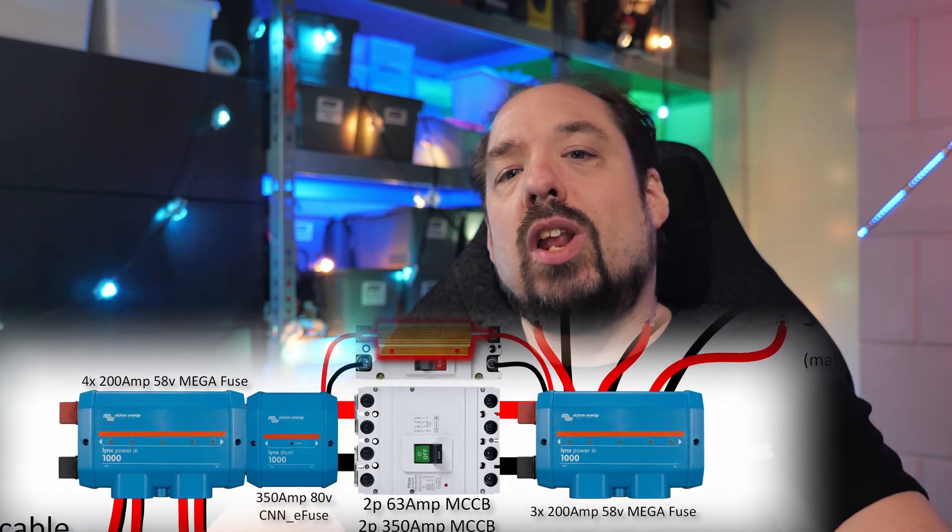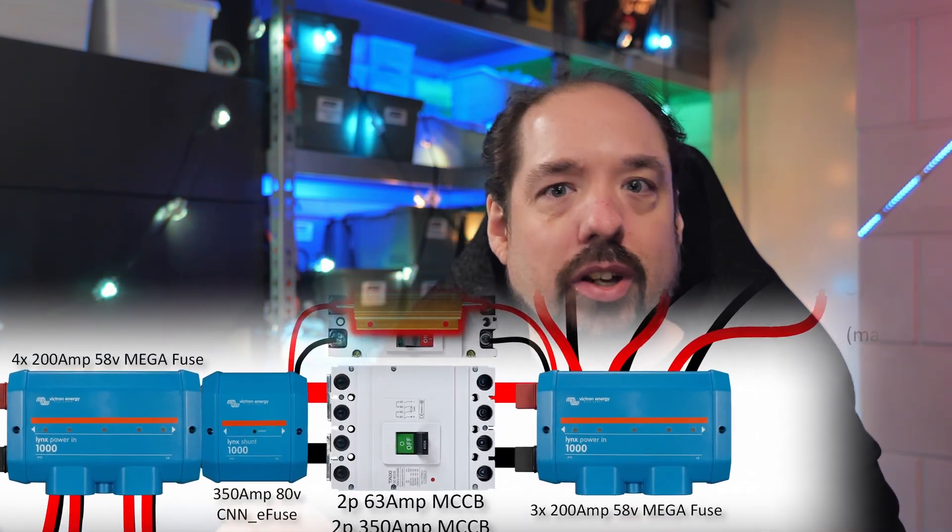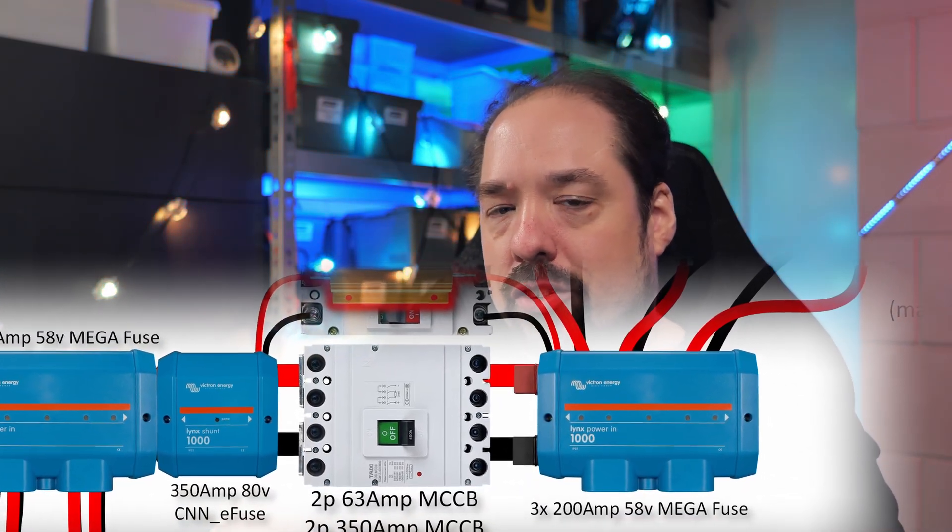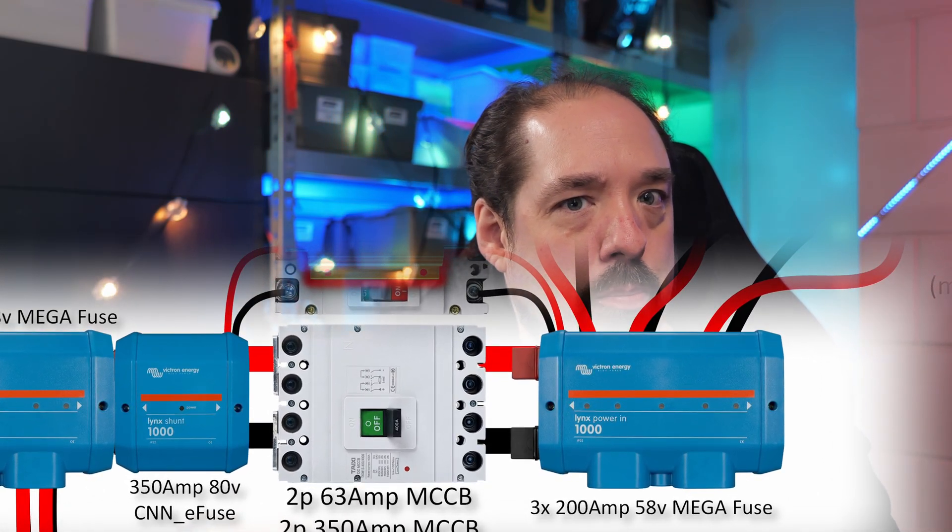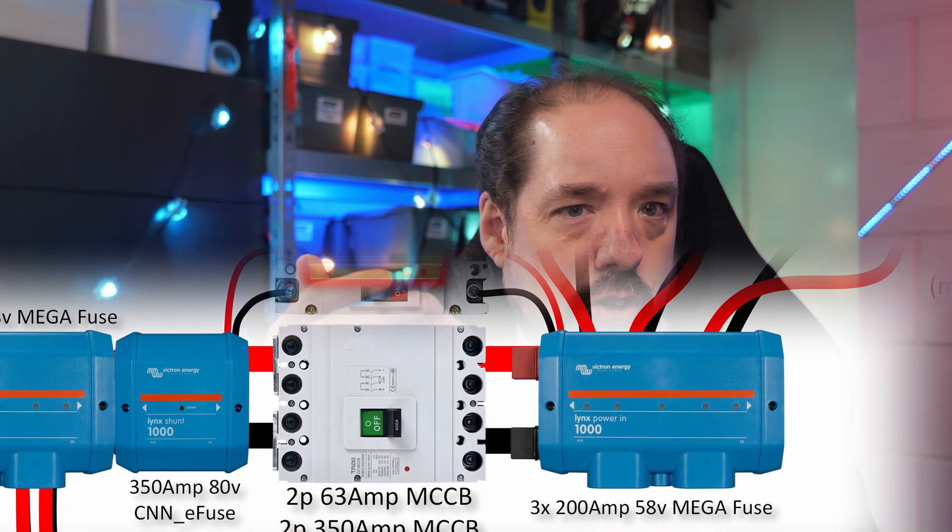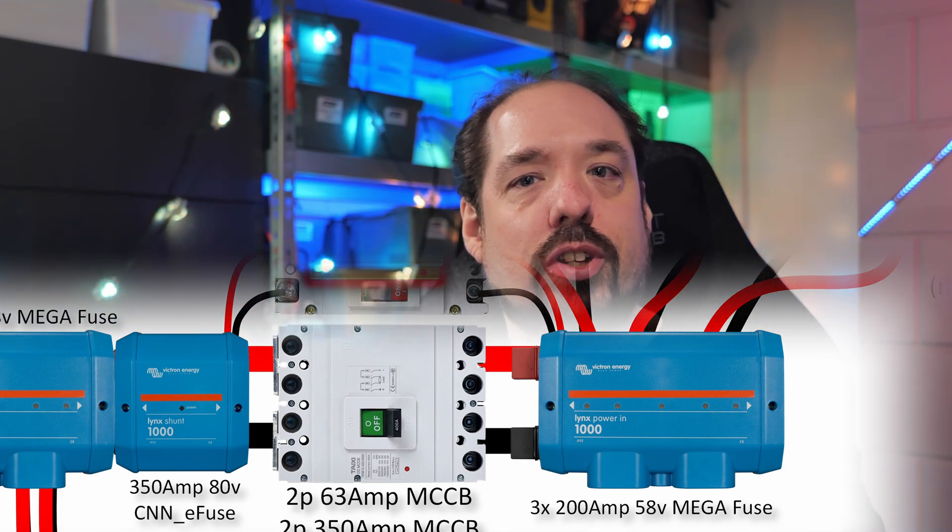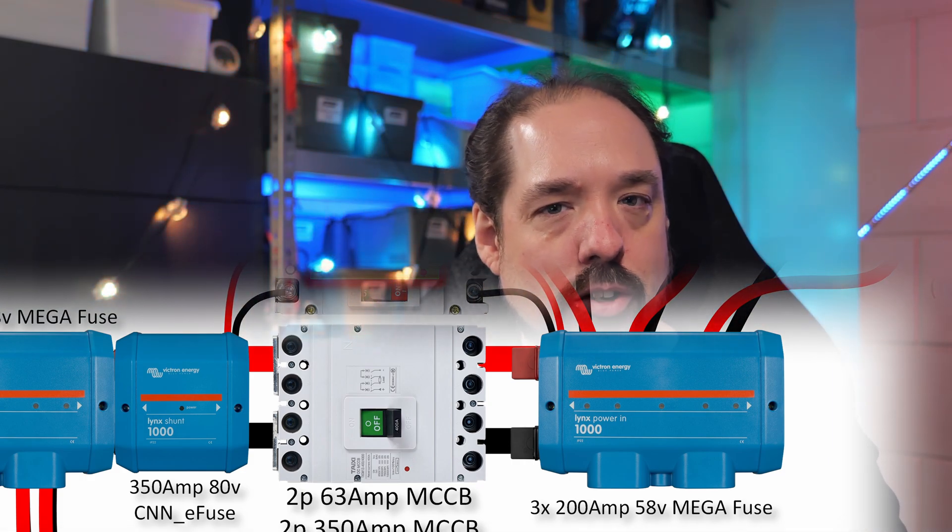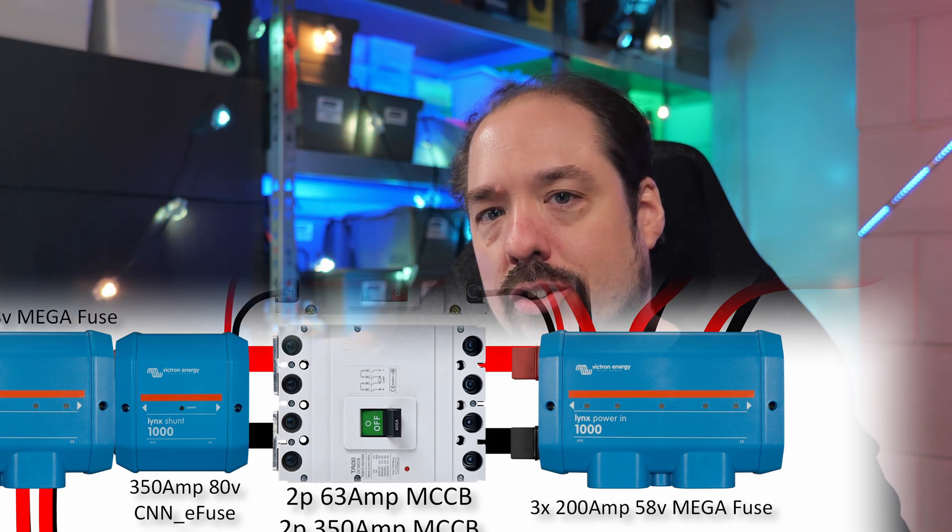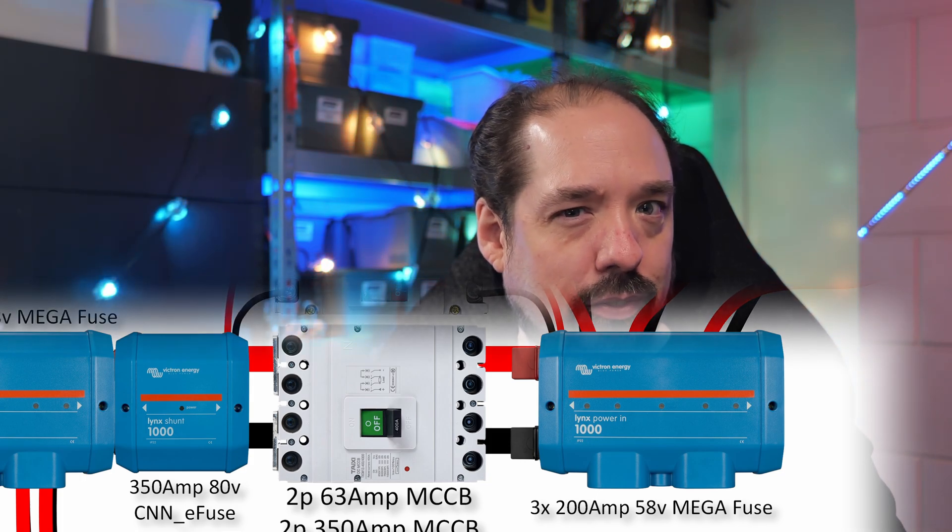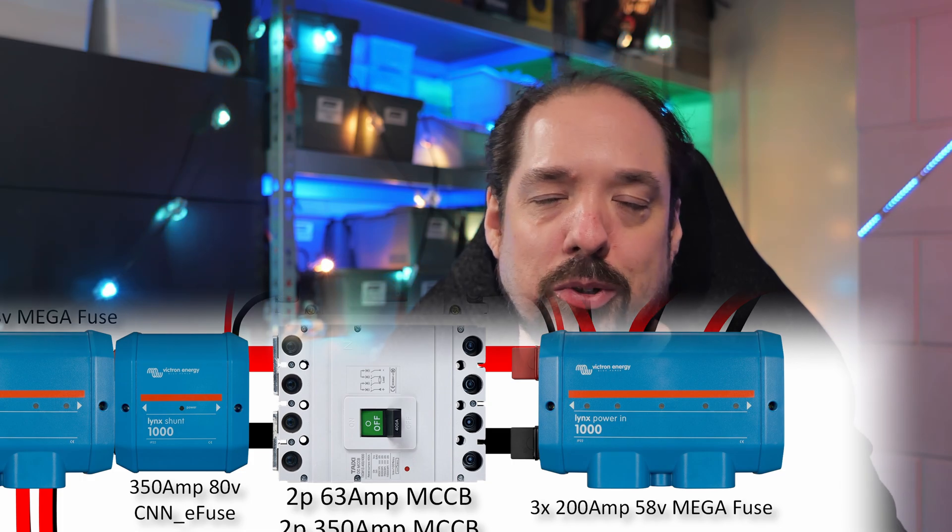Okay, let's continue. We are still in the left Lynx Power In, and fused everything into there. This Lynx Power In is then connected to a Lynx Shunt, which will measure the battery voltage, state of charge, and keep track of all those things independent of the battery box BMSs. In the Lynx Shunt, there is also a 350 amp fuse, just to be sure.